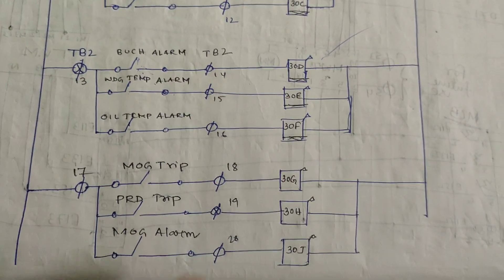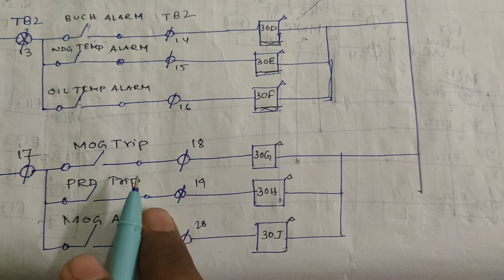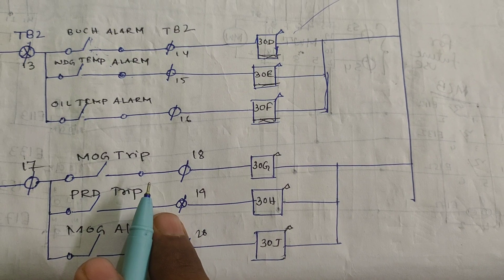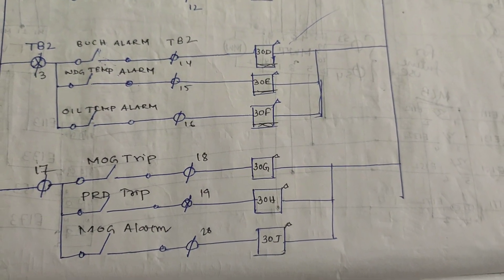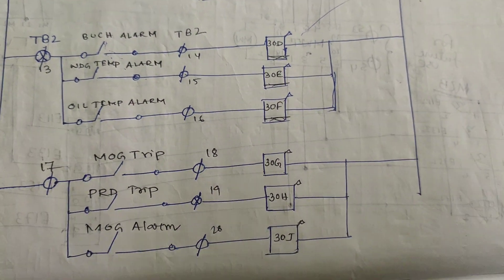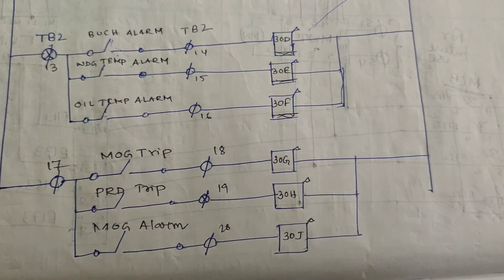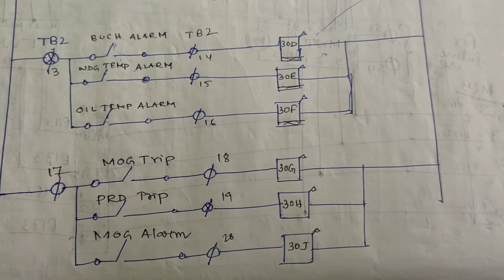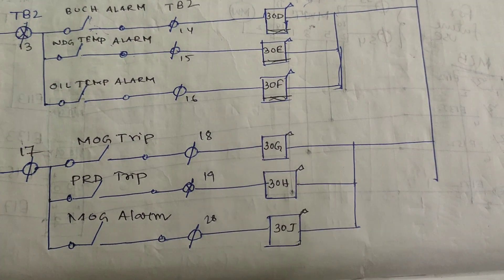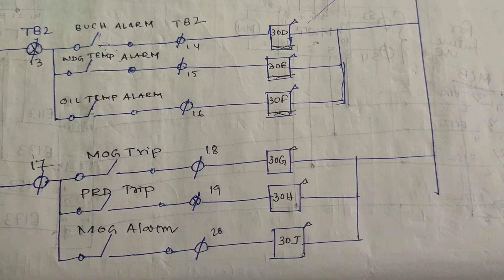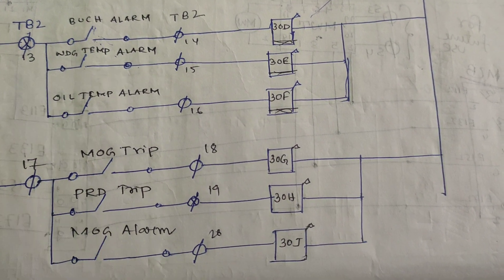The MOG — Magnetic Oil Gauge — is used in the conservator for oil level indication in the OLTC (On Load Tap Changer). If the oil in the OLTC reduces, the MOG level drops. If not observed, first the MOG alarm activates, then the MOG trip operates. This depends on the volume of oil — when oil reaches zero, MOG trip may occur because tapping cannot be changed without oil.